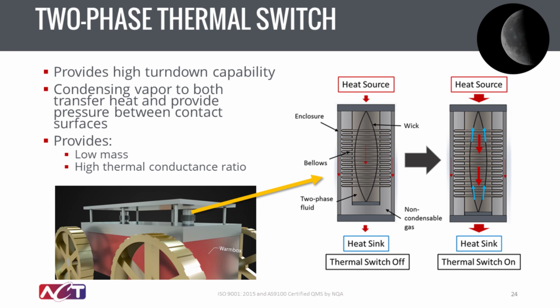The two-phase thermal switch, this is the smallest of our options. It provides a high turn-down capability, and it's combining a, we'll say, more traditional heat pipe with an internal bellows. So as you can see in the image more towards the center, this is the bellows being retracted. You can see the difference in the bottom from the center to the right-hand side. When it's retracted, the heat source is very little, and the working pressure of the working fluid allows that to be retracted. As the heat source increases, that allows the bellows to make contact with the heat sink and be able to reject that heat. So very high turn down capability from on to off, and also high power carrying capacity considering the small volume that it is.